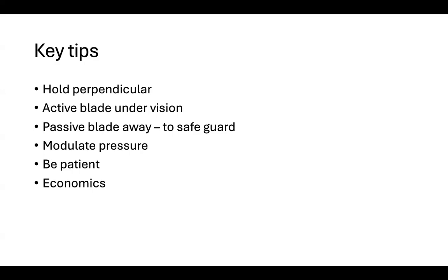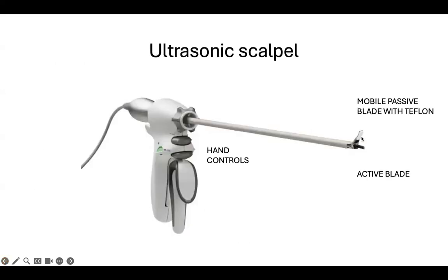Because the passive blade, that is this blade with the Teflon coating, is designed in such a way that there is no energy transmission here. There is no vibration, there is no energy transmission here. So even if you touch it against a bowel and activate the instrument, nothing is going to happen, because only the active blade is going to get activated. This is one beautiful aspect of this instrument, which is not seen in most of them.